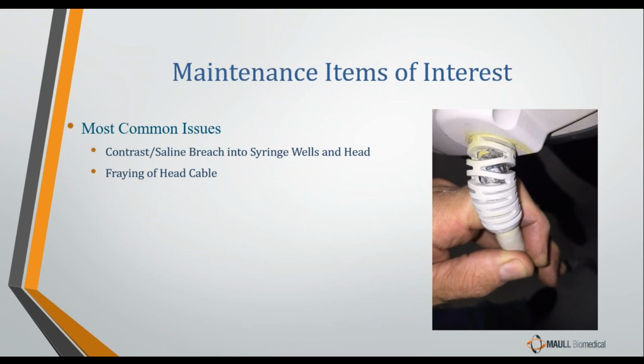One of the other most common issues with a lot of contrast injectors is fraying of the head cable. I said there's three components to every injector. There's the head, the display, and the main unit. The injector head has a cable coming out of it that connects to the main unit. That cable is called the head cable.